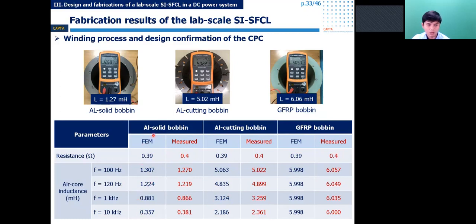The coil inductance was measured by the LCR method with different frequencies. From this result, we can see the effect of the eddy current loss in the metal bobbin on the coil inductance. With the higher frequency, the higher the eddy current loss, so it greatly reduces the coil inductance. That's the reason why the aluminum solid bobbin has a low performance for the fault current limit.